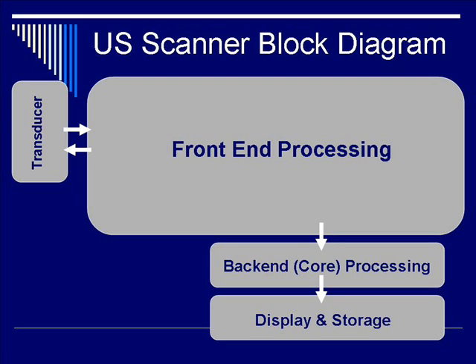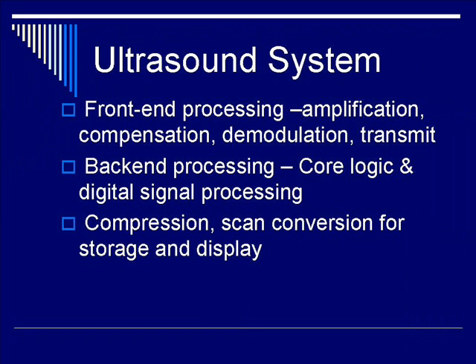On the left-hand side you have the transducer, discussed in the previous lecture. Signals flow in and out through the front-end processing block, which feeds into the back-end core processing block, then into display and storage. An ultrasound system basically contains these three big blocks. Front-end processing handles amplification, compensation, demodulation, and transmission. Back-end processing crunches the numbers. Finally, compression and scan conversion are used for image storage and display.